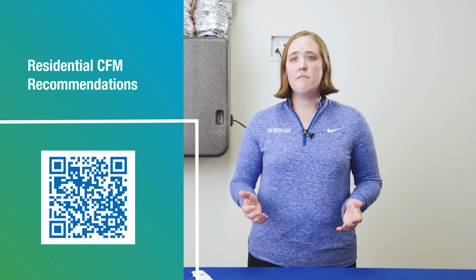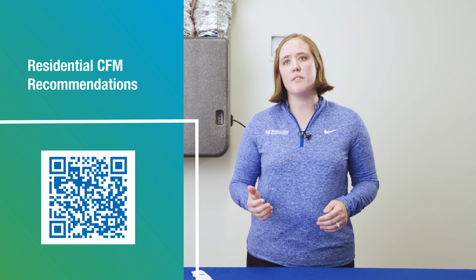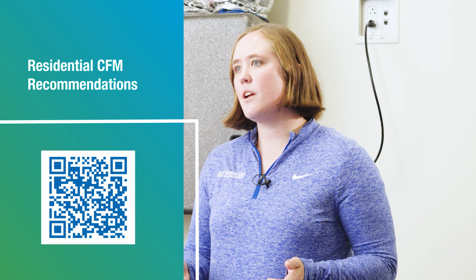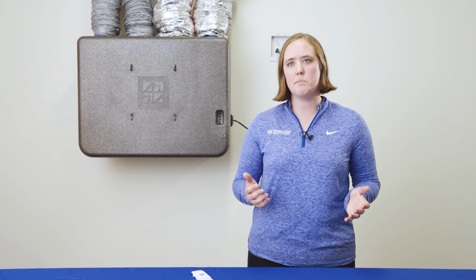For assistance in determining correct airflow settings, visit RenewAire's residential ERV landing page. This site will provide an ASHRAE recommended minimum low speed or continuous ventilation rate for residents based on square footage and the number of bedrooms. The resulting airflow can be used as a guide and modified as desired using the steps laid out in this video.